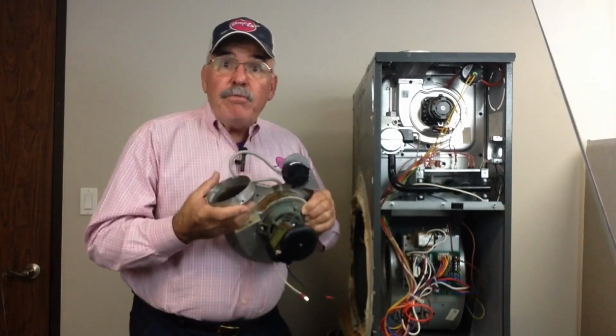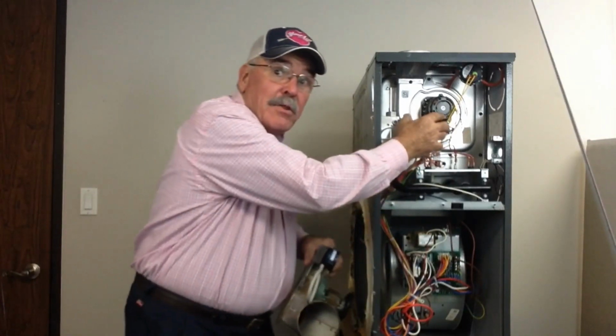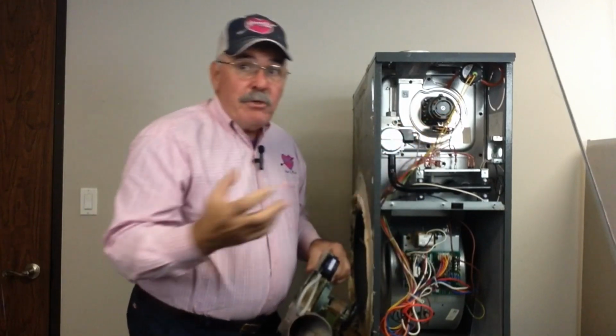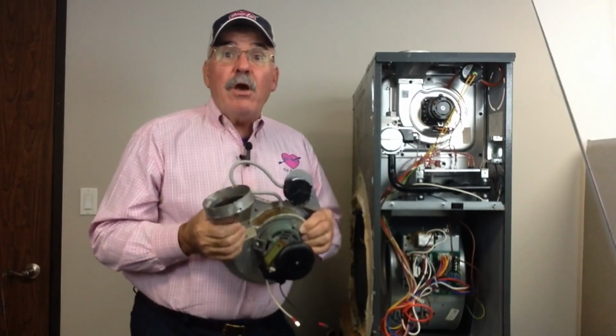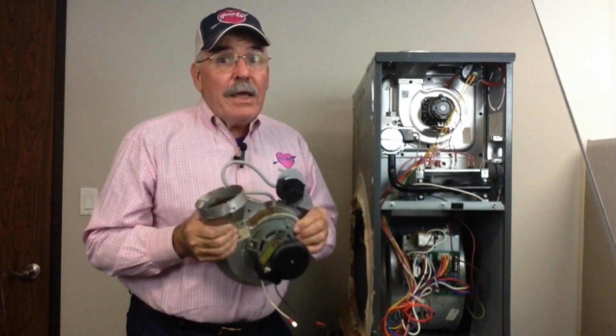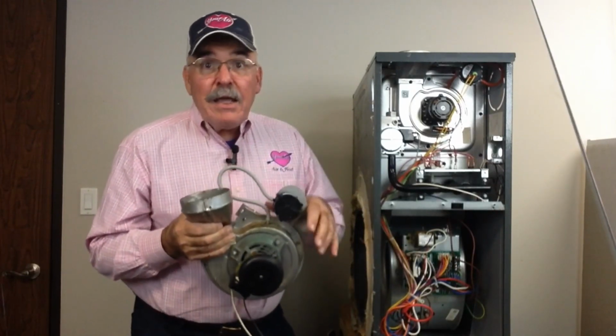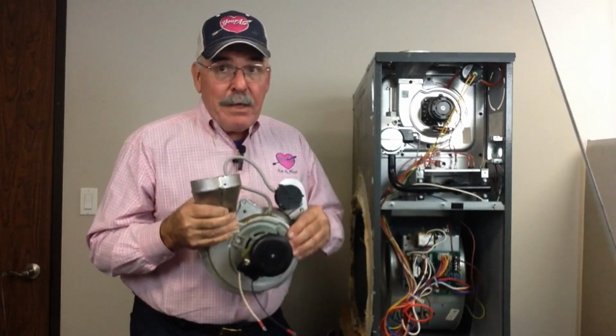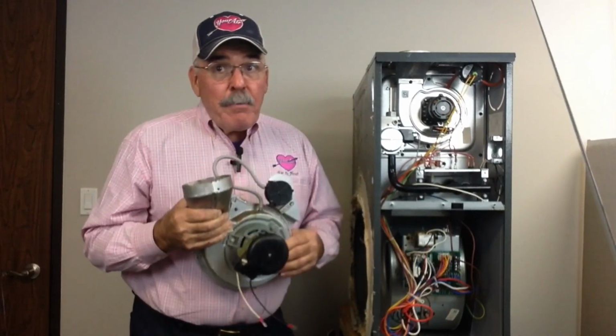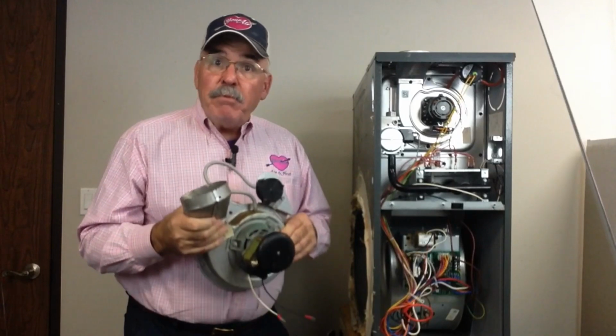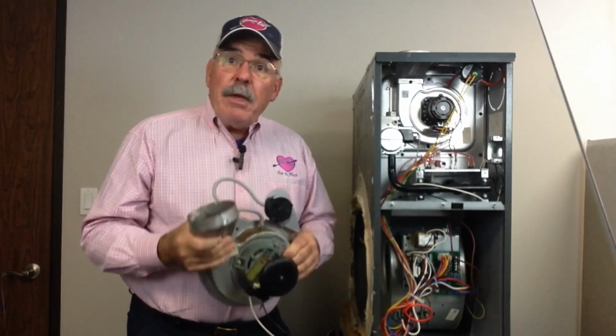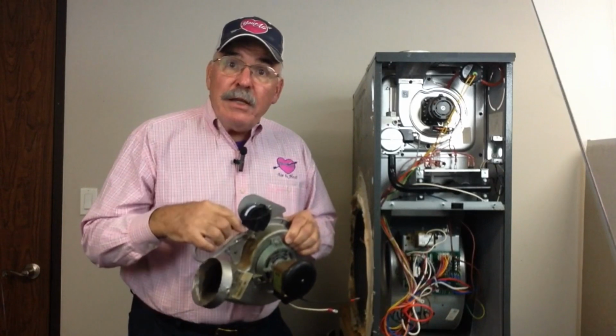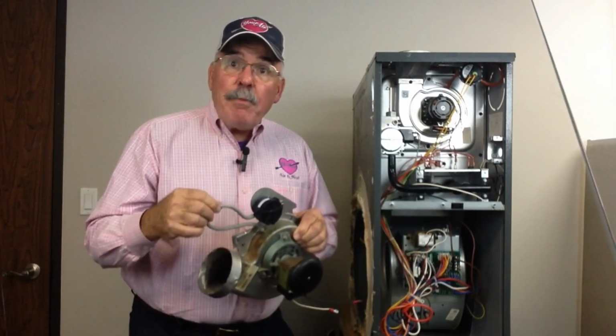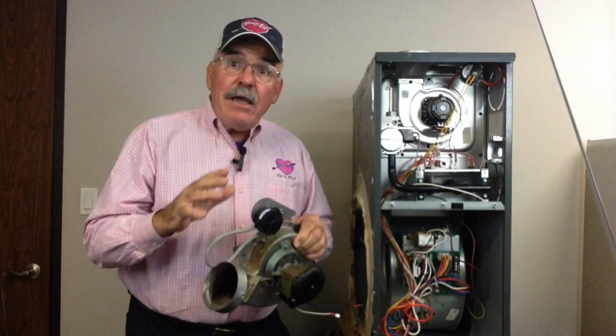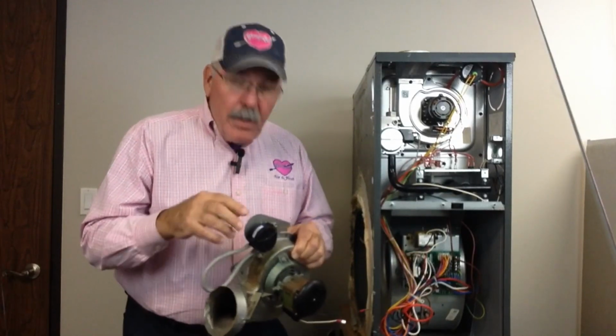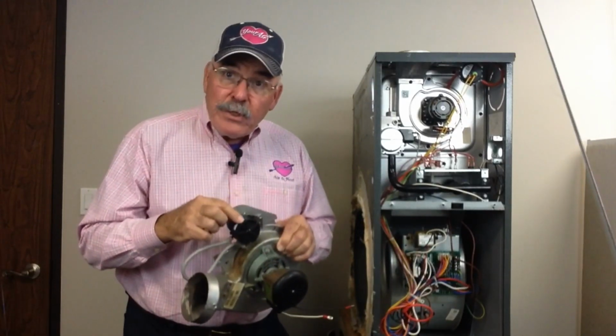Now because the inducer fan assembly itself is attached in here to the heat exchanger in the flue pipe, as the furnace operates, this component is going to go under periods of rapid heating and cooling, so condensation from the heating and cooling can easily form in this assembly. This condensation that will build up in here is full of minerals and impurities from the flue gas as it moves, and the impurities can clog either the ports in the inducer assembly right here or stop up these vacuum hoses, which lead to the second critical safety device in our furnace that I pointed out a second ago, called the pressure switch right here.